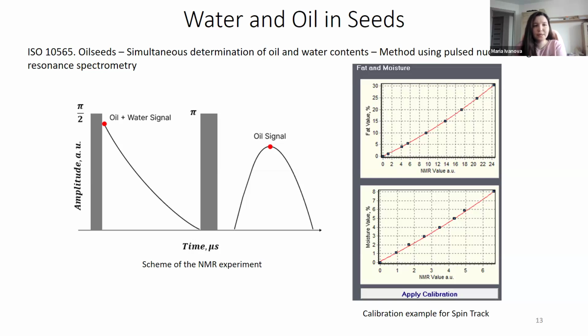From the first 90-degree pulse, the sum of the oil and water signals is recorded, and after the pi-pulse, the oil signal is acquired as the spin echo signal. Thus, we can differentiate the contributions of oil and water and build separate calibration curves. In the calibration, the known reference moisture content is matched to the NMR value recorded by the NMR system.